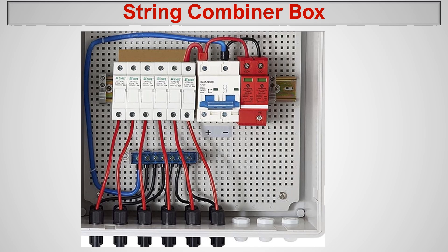Inside we have fuses for each string, then a large circuit breaker that combines all the power together, and a surge protection device — this output goes to the inverter, or to a battery if one is installed. By opening the combiner box you can clearly understand the system size. We have six strings, so it's quite a large system. By looking at the fuse and circuit breaker ratings, you can see the current rating — 20, 30, or 40 amperes — which is very useful information.